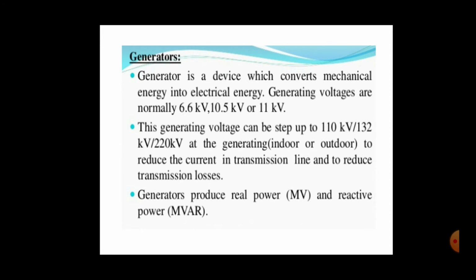Next, generators. A generator is a device which converts mechanical energy into electrical energy. Generating voltages are normally 6.6 kilovolts, 10.5 kilovolts or 11 kV. This generating voltage can be stepped up to 110 kV, 132 kV or 220 kV at the generating station, indoor or outdoor, to reduce the current in the transmission line and to reduce transmission losses. Generators produce real power in megawatts and reactive power in megavolt ampere.